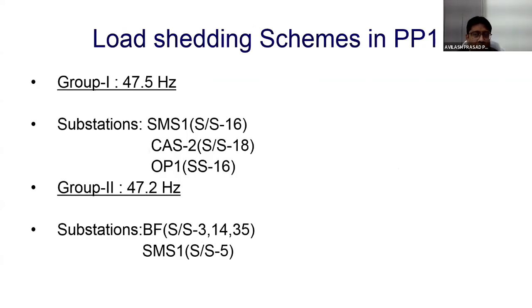So in our PP1, what we call the captive power plant, in group 1, 47.5 Hz, we have 3 substations. We have connected these substations for shedding at first instance, that is SMS1, which is substation 16, CAS2, that is compressed air station 2, which is substation 18, and OP1, oxygen plant 1, that is substation 16. In group 2, that is the 47.2 Hz category, we have the substations of BF, that is substations 3, 14 and 35, and SMS1, that is substation 5.